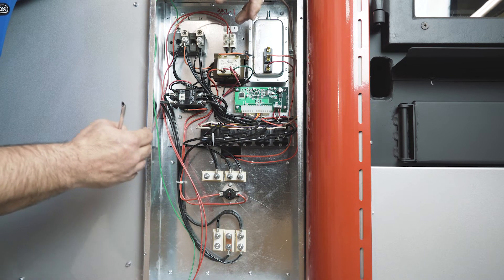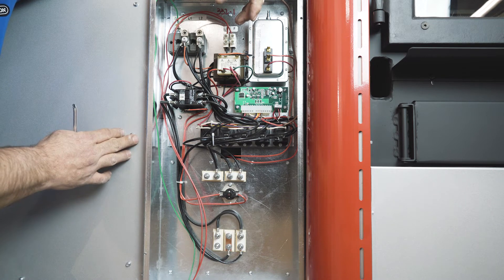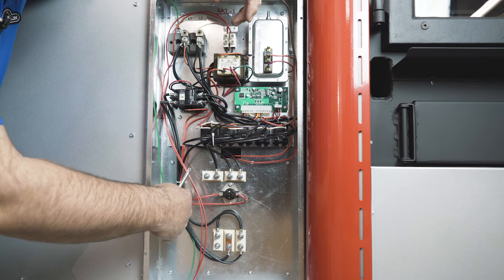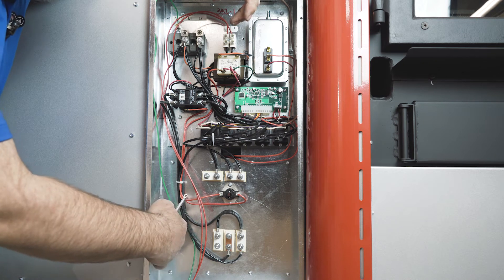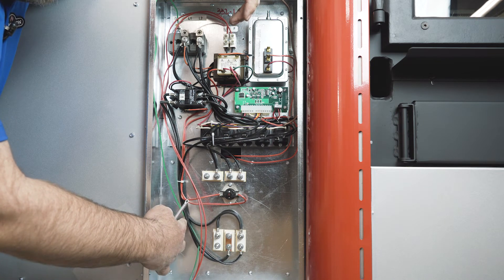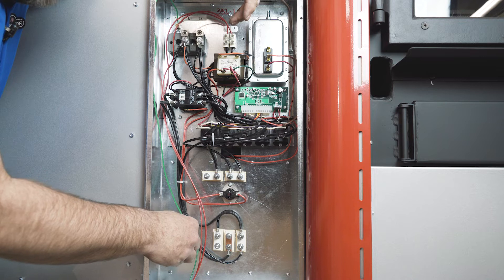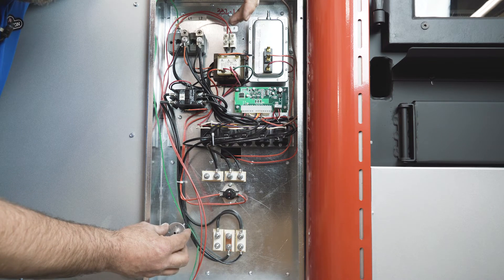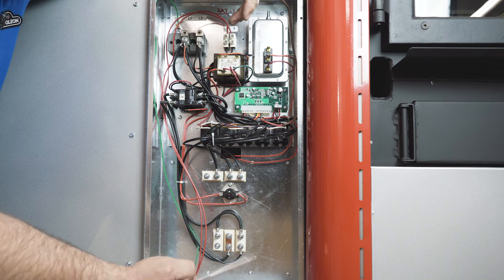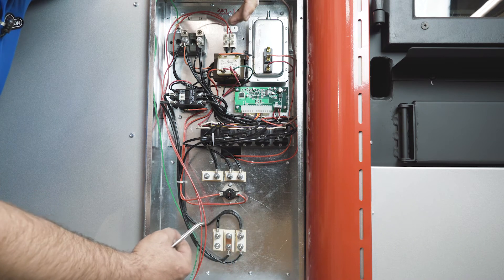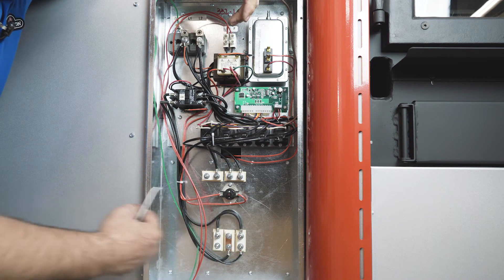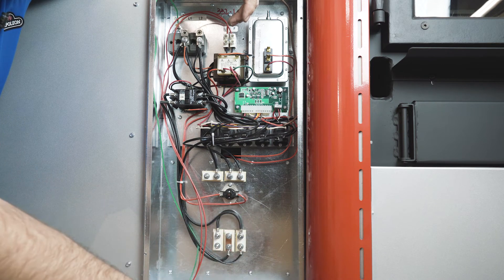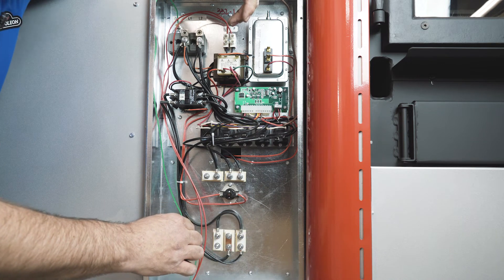So if your blower module is on this side, you will place a hole about 6 inches up, about an inch and a quarter off the side. A 3/8 inch hole. You'll install this tube with the opening in the direction of the air flow. Our air flow is coming this way, so the opening would be towards the air flow.